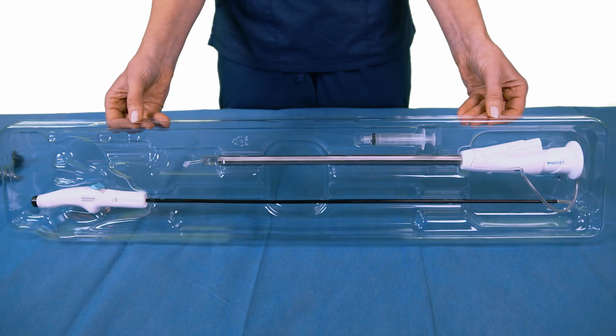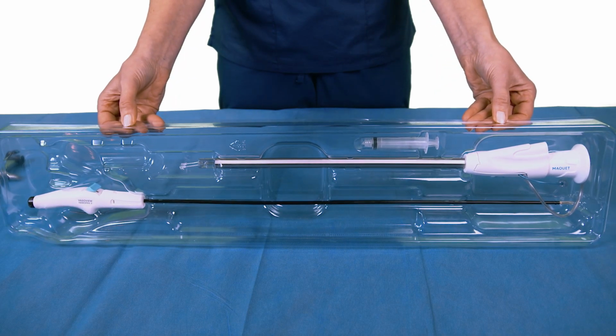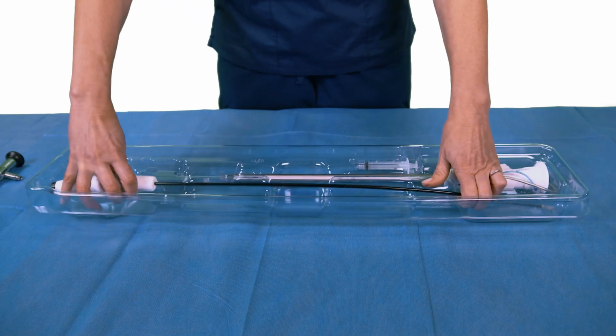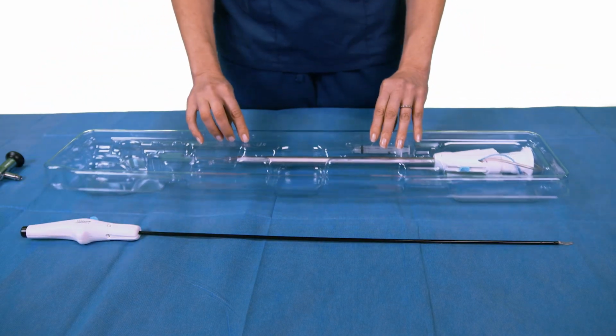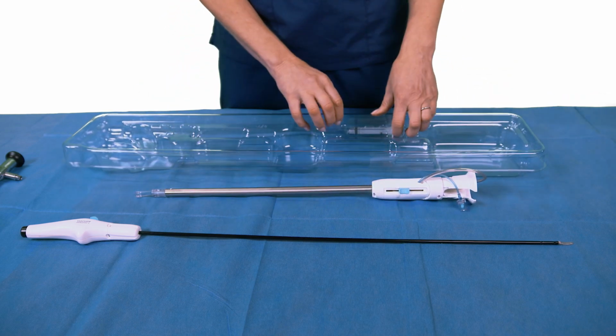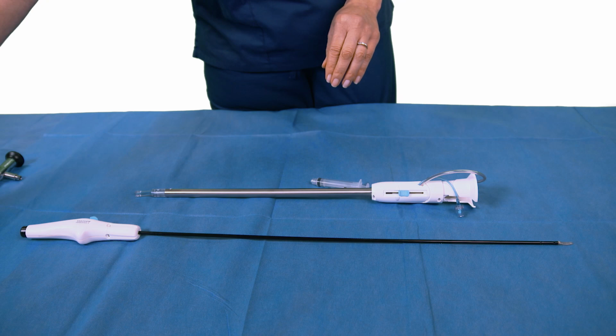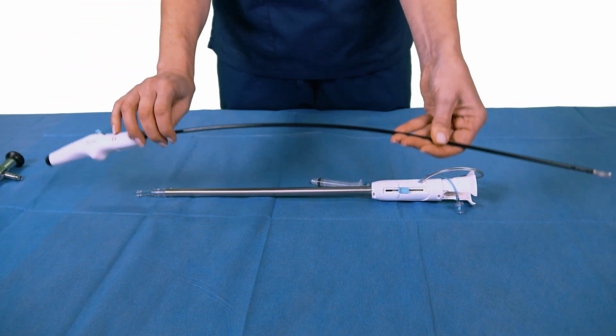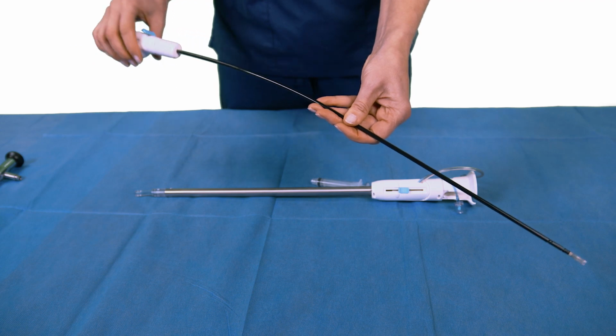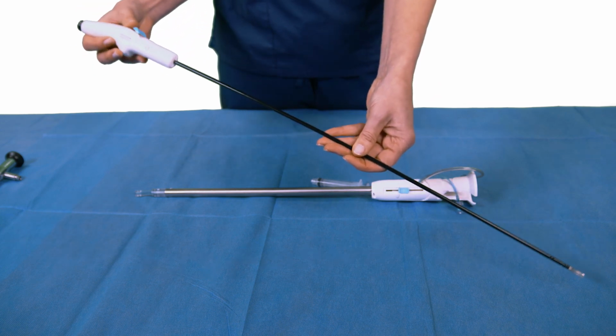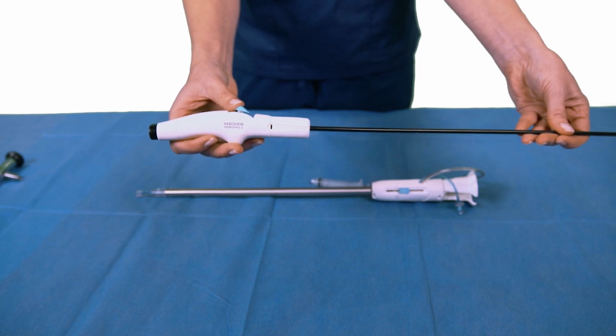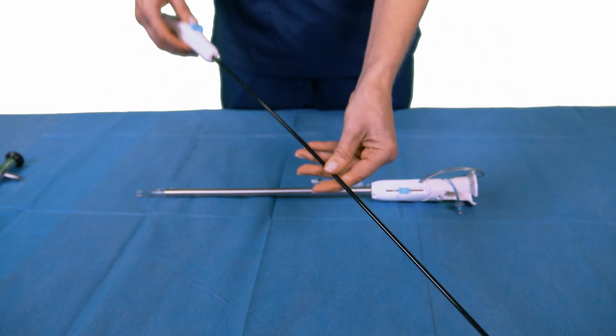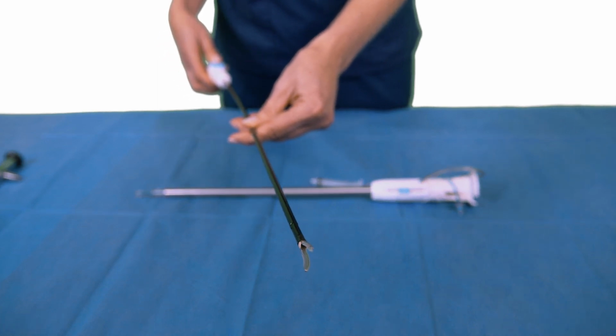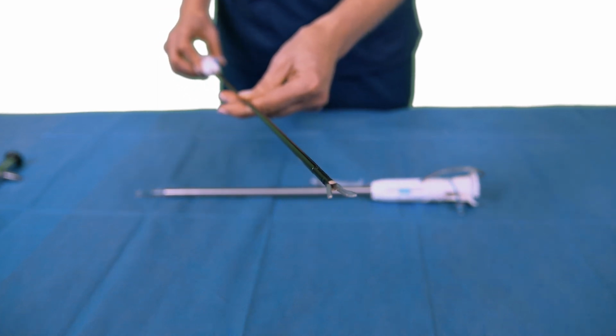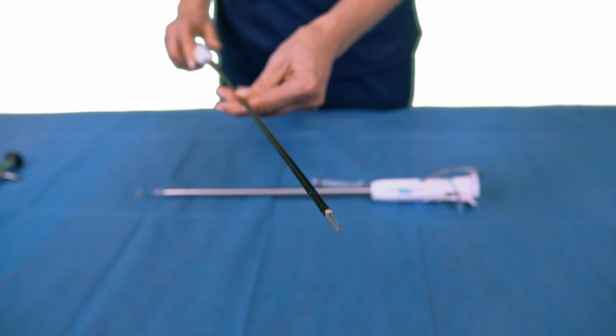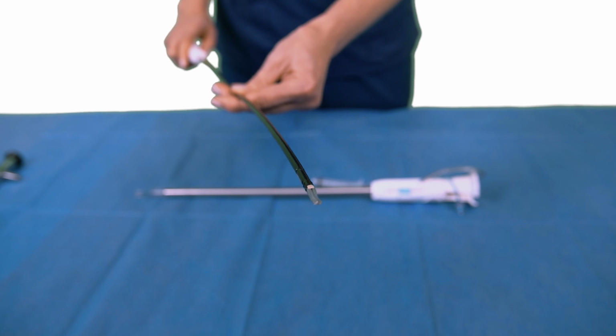In the remaining part of the tray is the transection equipment. This equipment consists of the Hemopro 2 cutting tool, the cannula, and a 3 cc syringe. The Hemopro 2 cutting tool cuts and seals vessels in one easy step. The activation toggle on the handle controls the jaws. To open the jaws, you would push the activation toggle forward. To close the jaws in the middle, and to activate the device, you would pull completely back.